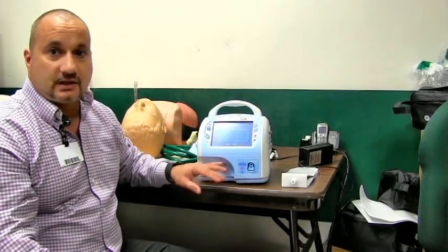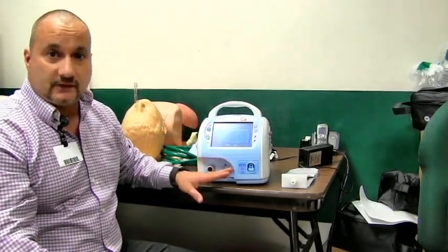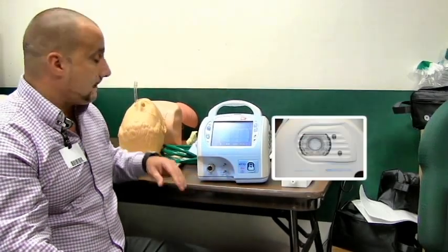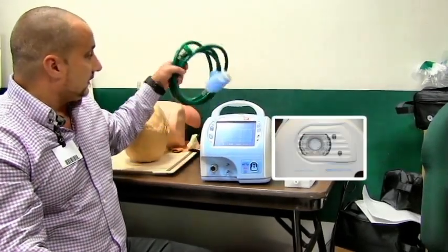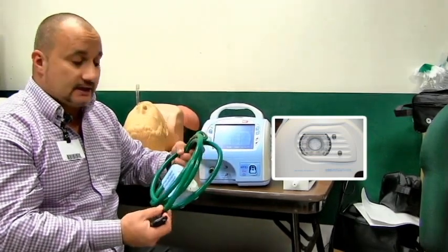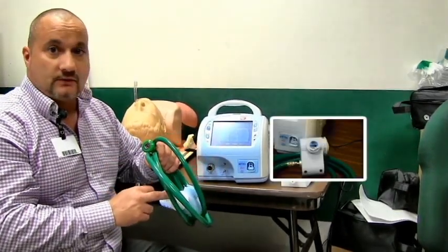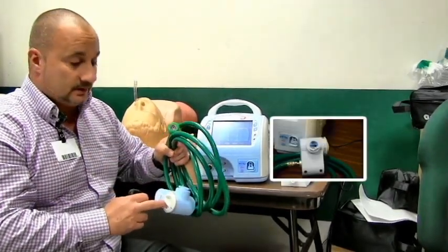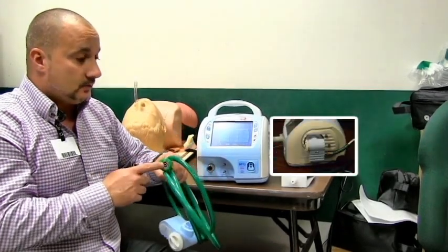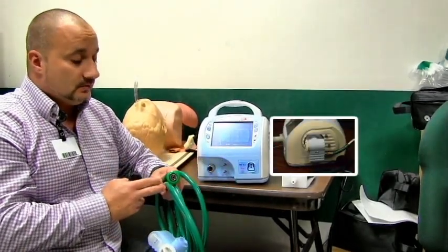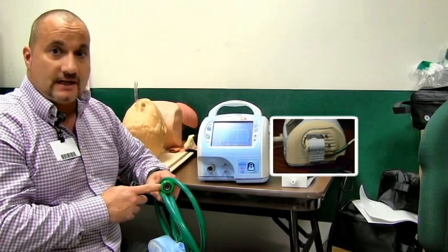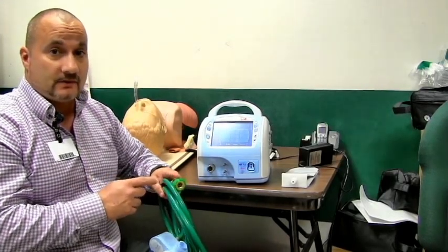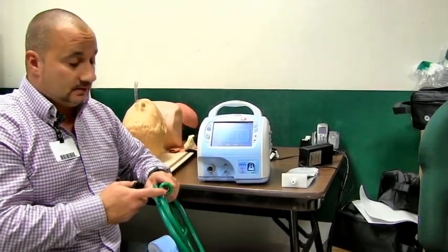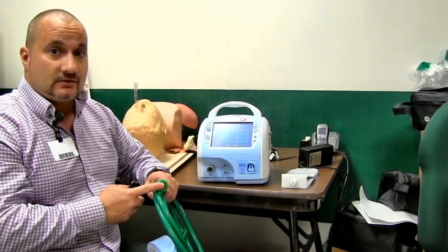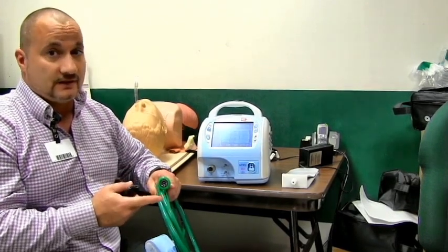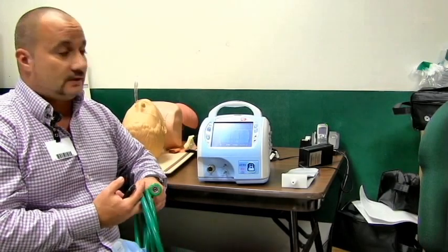It's gone through its basic internal setup and it's ready for our interface with the unit. Just as a side note, don't forget that we do have your high pressure line that you'll need to connect with the dial flow for the FiO2 based upon your patient's needs. The high port connects to the tank. Make sure that you have a tank, especially if you're going to have any travel time whatsoever, and have a decently full tank to transfer the patient, especially if they're in a high FiO2 setting, because it will suck through oxygen relatively quickly.